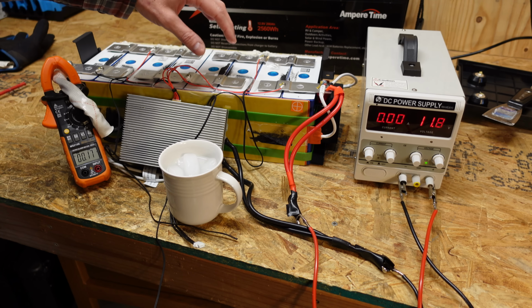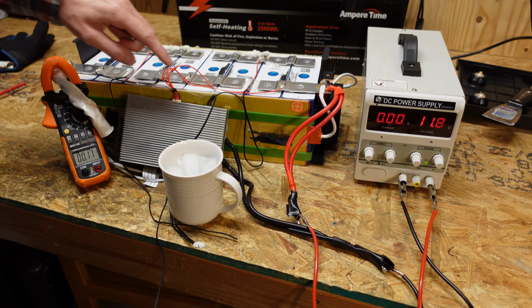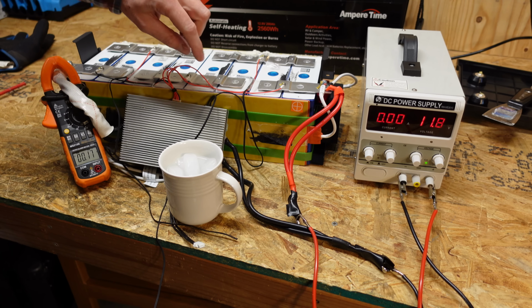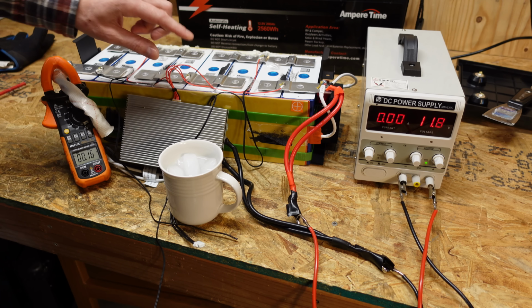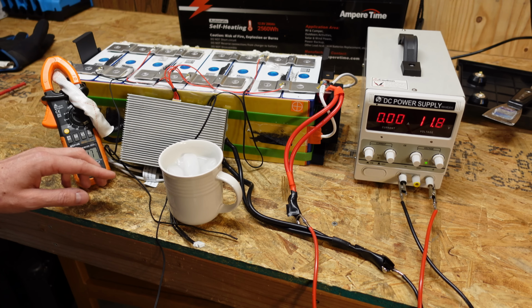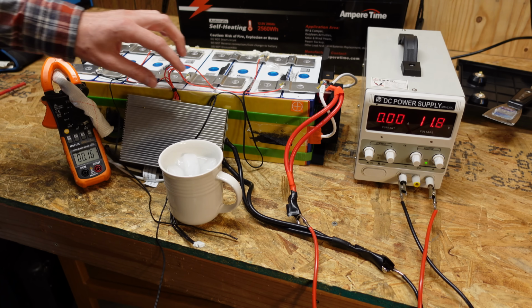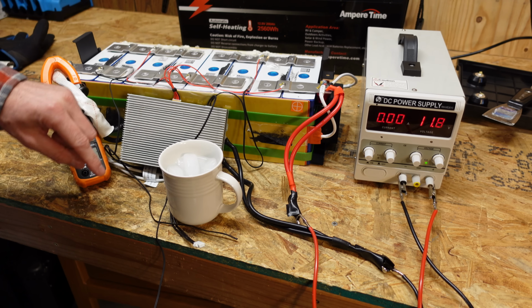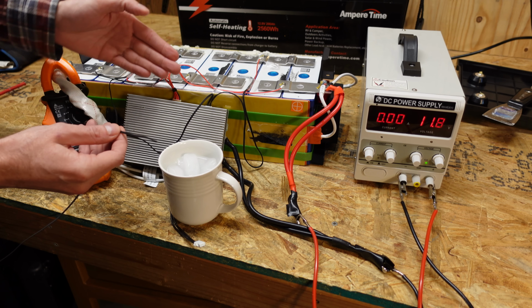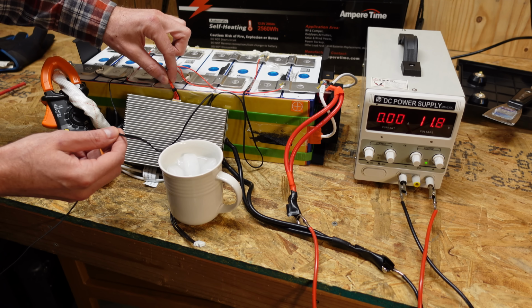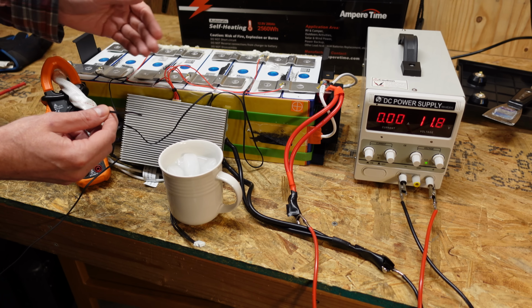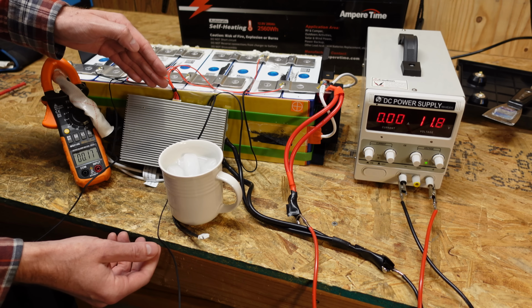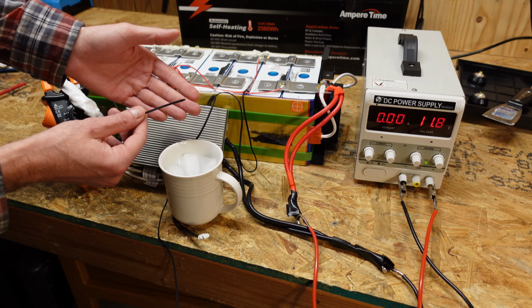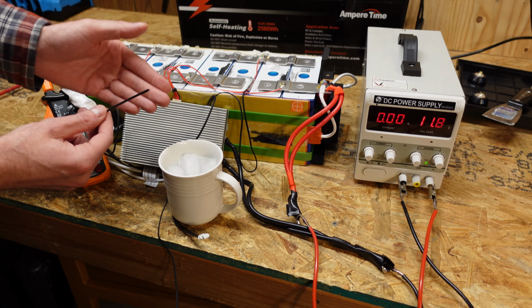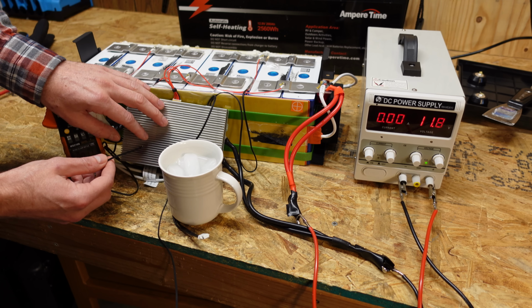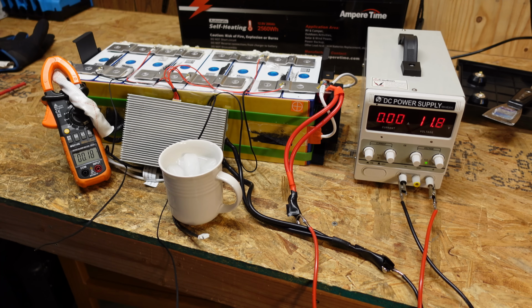There are 4 temperature sensors on this battery: 2 on top of the BMS where the balance leads go in, and 2 on the bottom where the heater leads go in. It turns out these sensors have 2 separate functions. The one by the balance leads is for charge protection, telling the BMS when it should and shouldn't charge. The one by the heating elements tells the BMS when to turn the heater on and off. I can demonstrate that here.